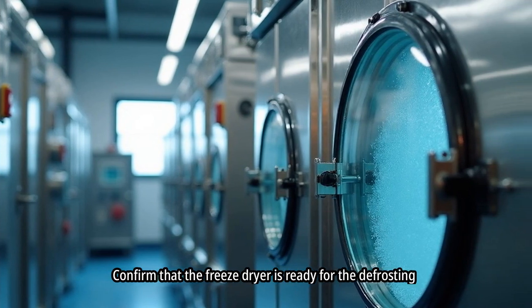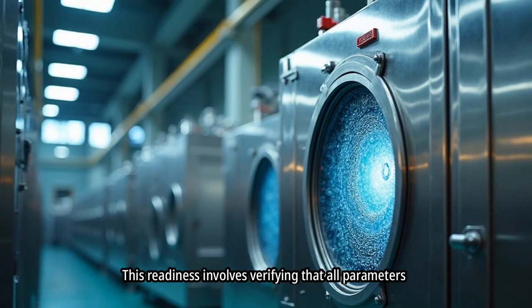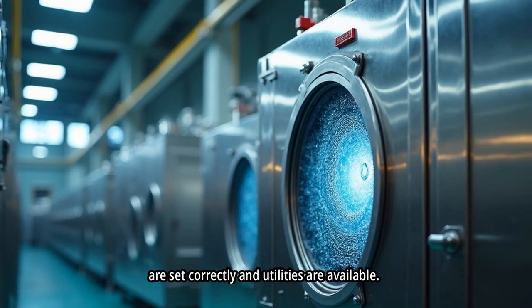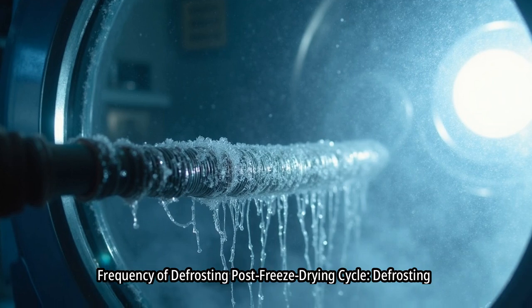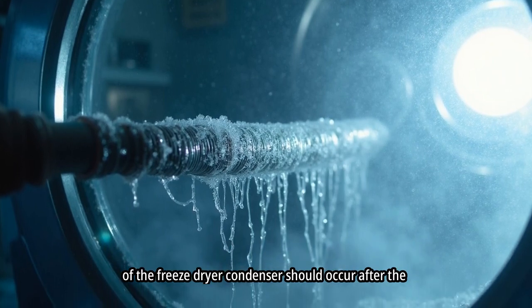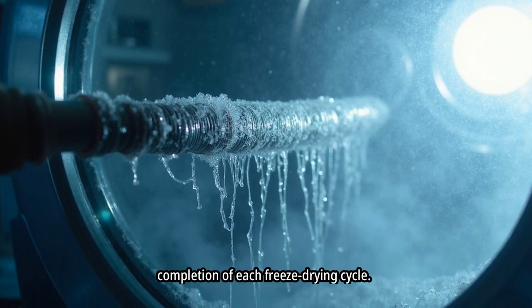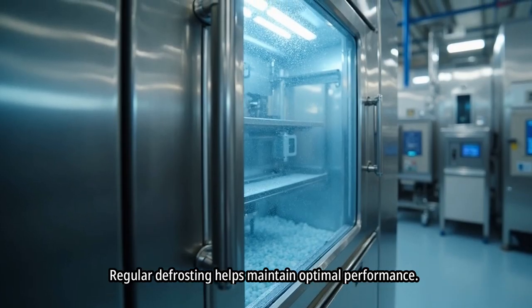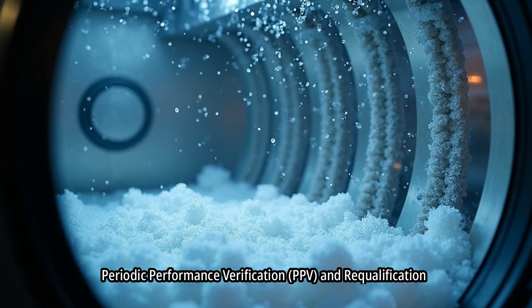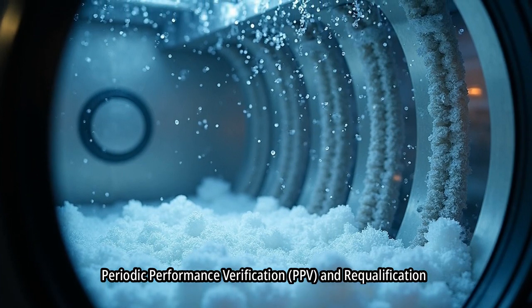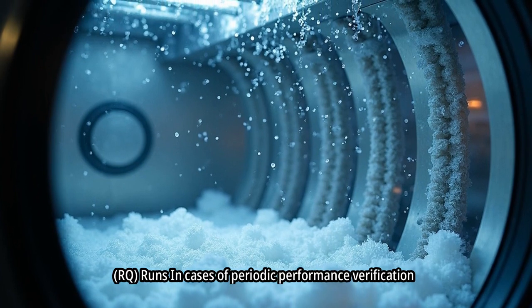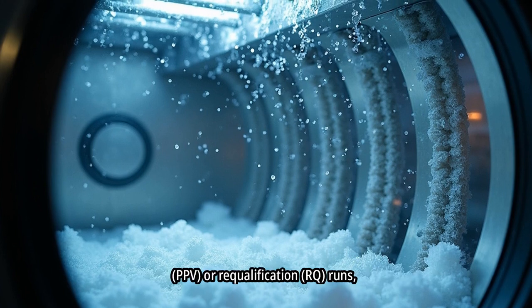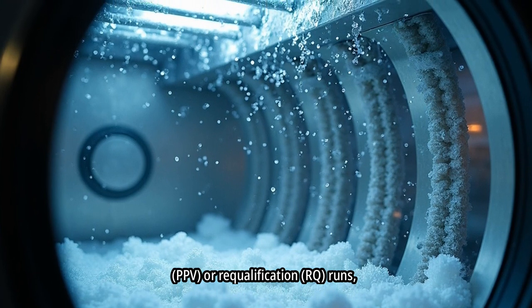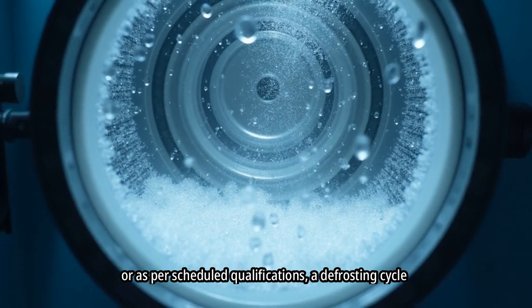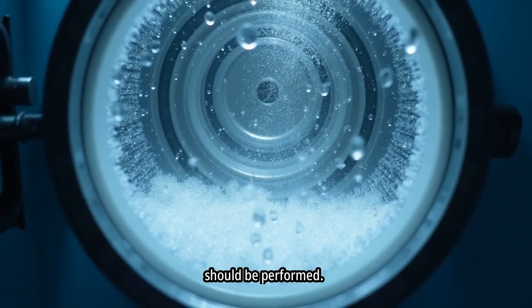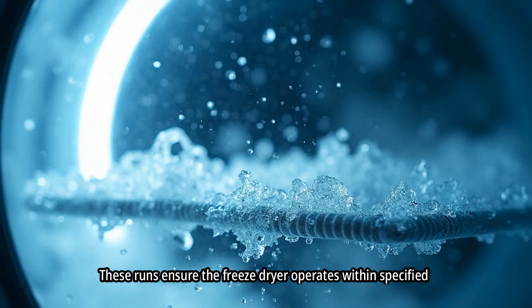Equipment readiness. Confirm that the freeze dryer is ready for the defrosting cycle. This readiness involves verifying that all parameters are set correctly and utilities are available. Frequency of defrosting: post freeze drying cycle. Defrosting of the freeze dryer condenser should occur after the completion of each freeze drying cycle. Regular defrosting helps maintain optimal performance. Periodic performance verification, PPV, and requalification, RQ, runs. In cases of periodic performance verification, PPV, or requalification, RQ, runs, or as per scheduled qualifications, a defrosting cycle should be performed. These runs ensure the freeze dryer operates within specified parameters.